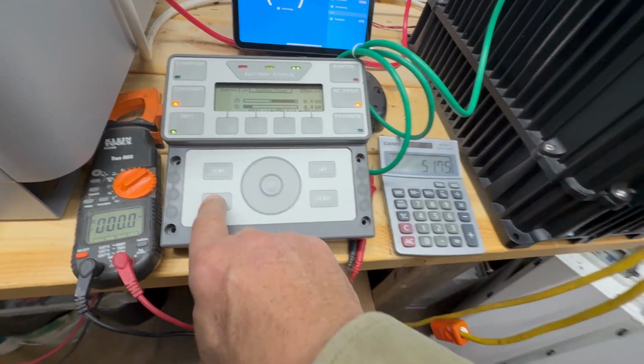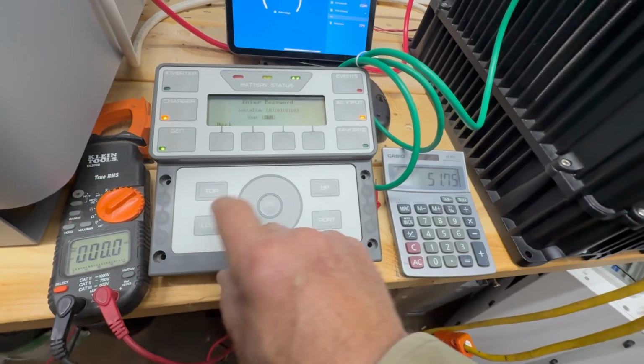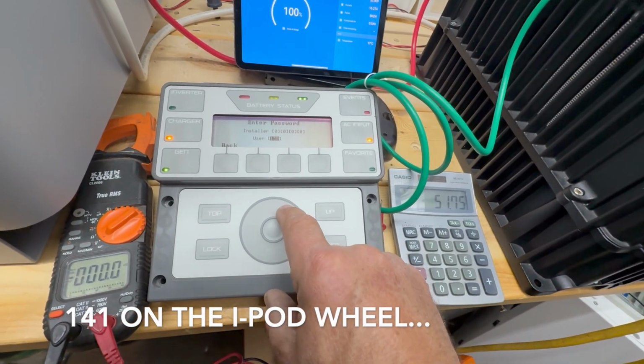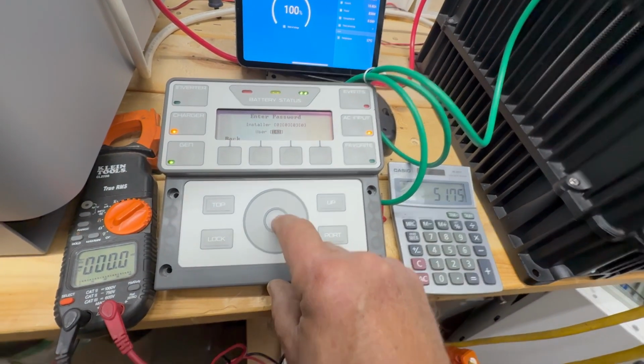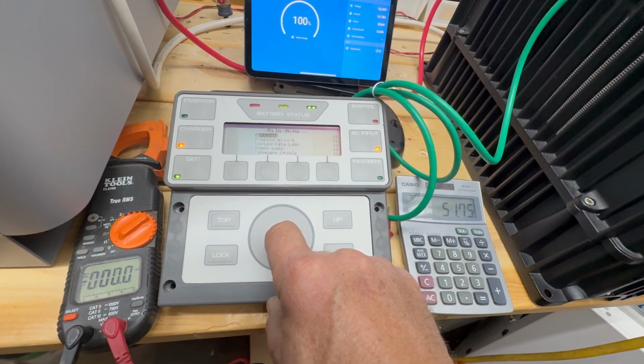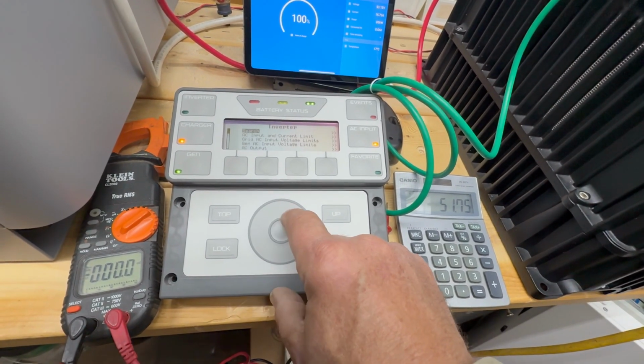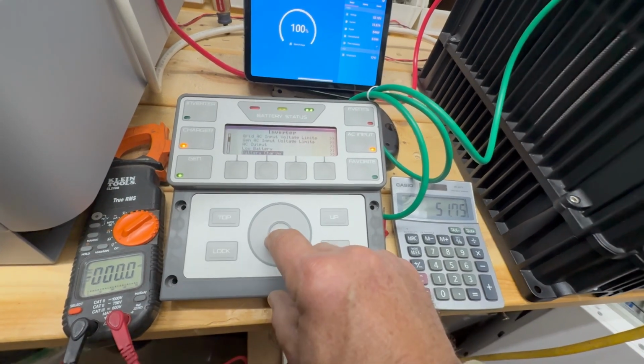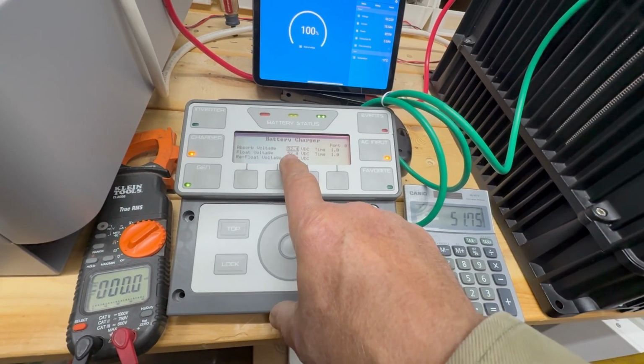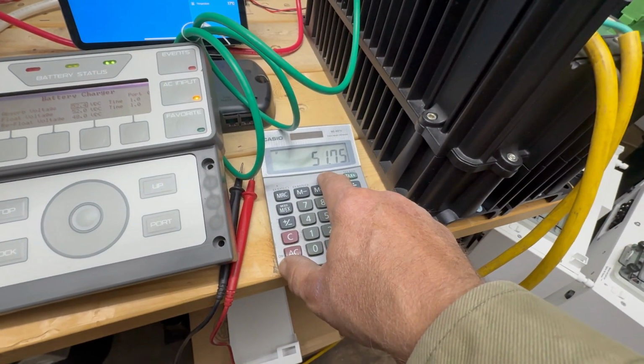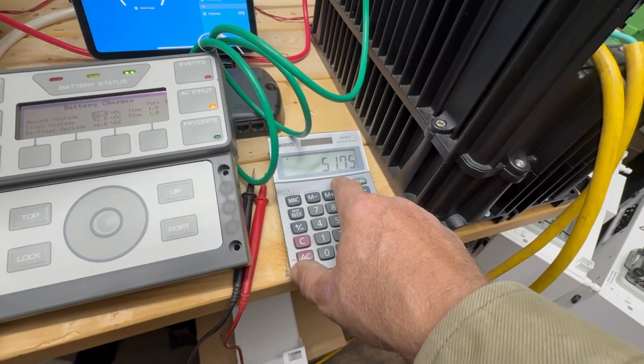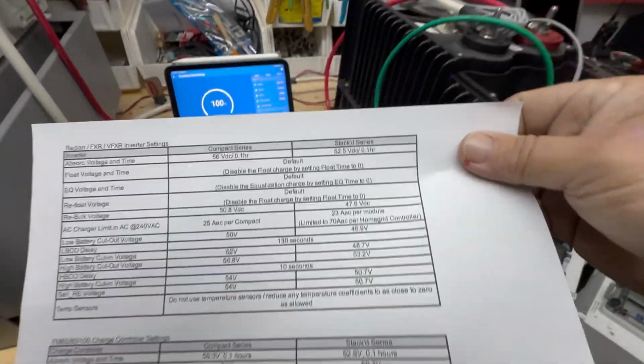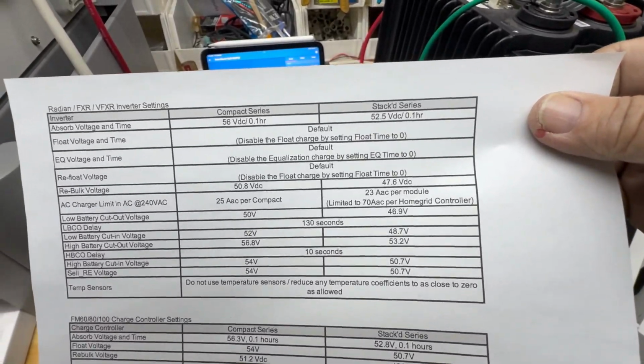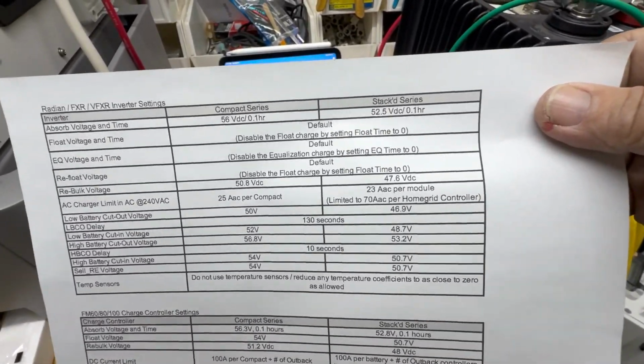I'll show you how to do that here on the mate of the Outback. We'll go to the installer password. Check. Settings. Inverter. Battery charger. I set 52.4, which is a little bit higher than the 3.45 volts I was telling you about, and a little bit lower than the manufacturer's recommended setting by just 1/10 of a volt.